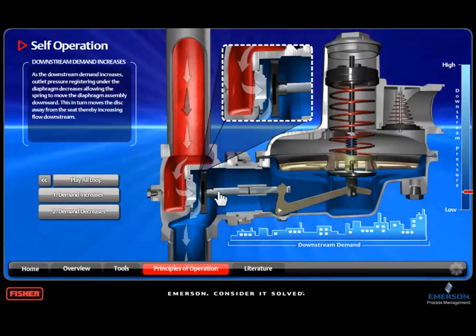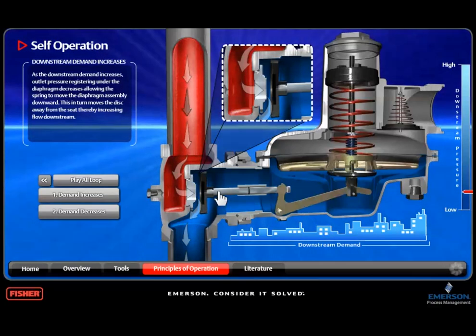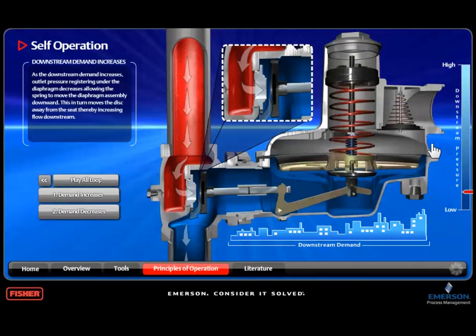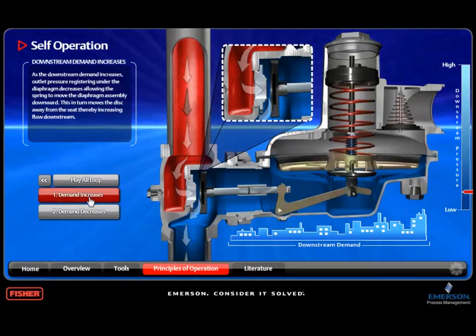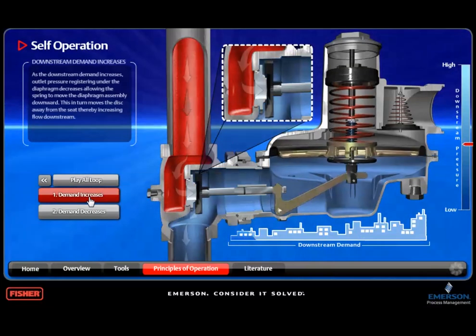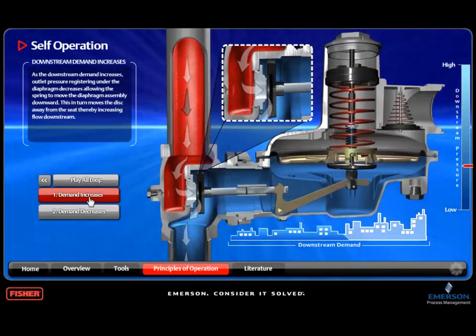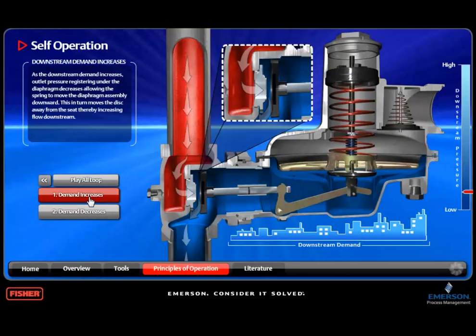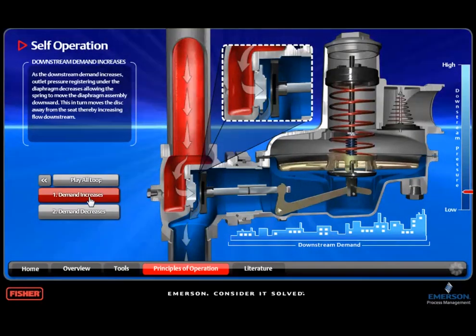Let's watch the animation again. This time pay attention to the pressure gauge shown on the right side of the screen and the downstream demand gauge below on the regulator. In order for the regulator to open to meet the increasing demand, outlet pressure has to decrease, and the outlet pressure will stay in place as long as the flow demand is high.